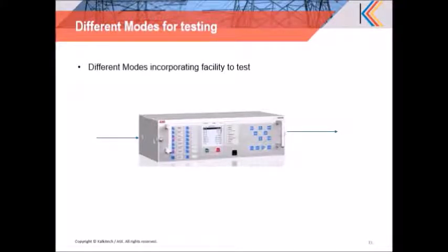Now moving on to the different modes for testing, that is, the different modes introduced in testing as per edition 2 of the standard. Consider an IED. Mode on: in this mode the output is enabled and test is false, so that only the actual data can be transmitted over the output. Test cannot be performed if you put it in mode on, as testing is false and output is enabled. Then mode blocked. In this scenario, output will be completely disabled and test is also false. No operation is permitted, including the actual forcing of output and test. So this is the second mode, mode blocked.